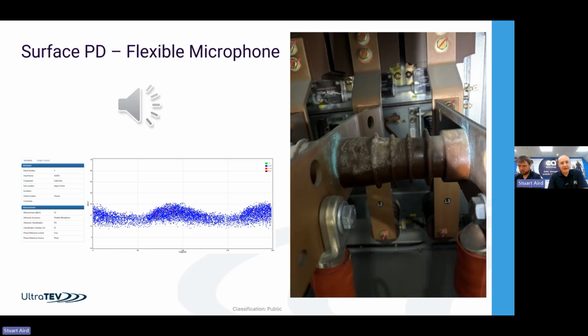Again, we picked up clear PD. This is just using a flexible microphone around the edges of the cable termination box on this particular panel, and we can hear the PD. I'll play that for you.